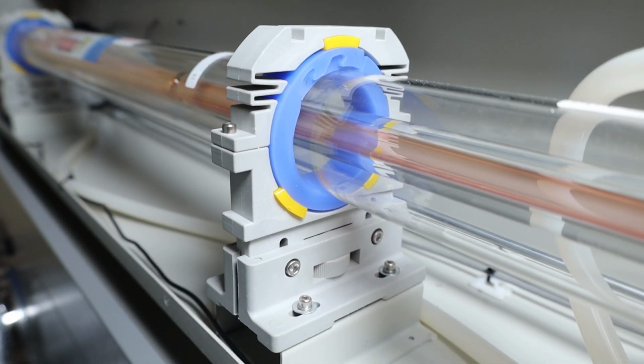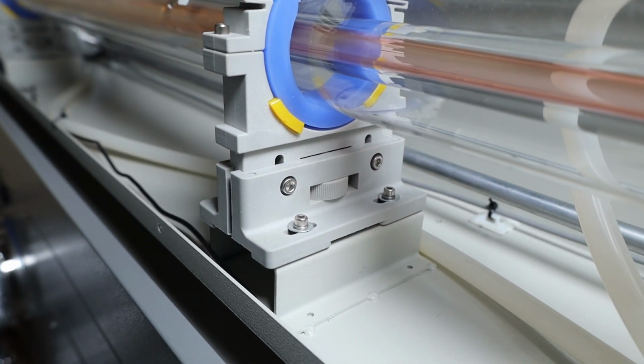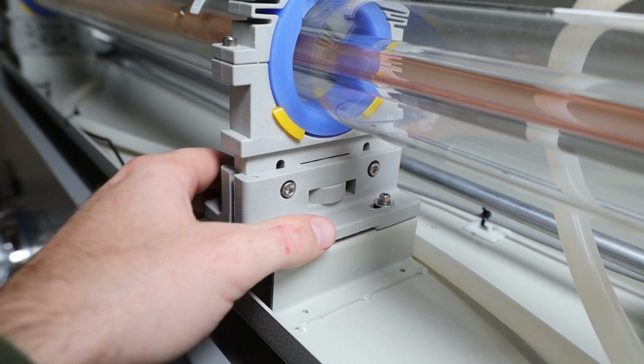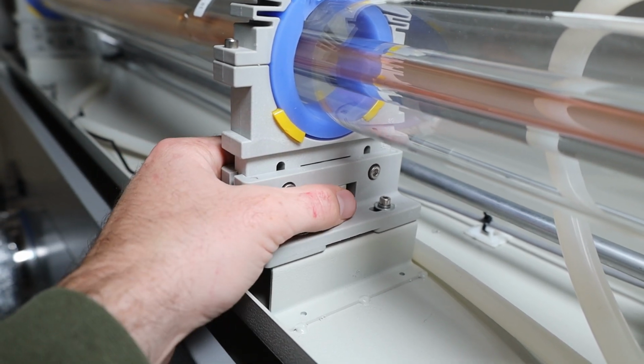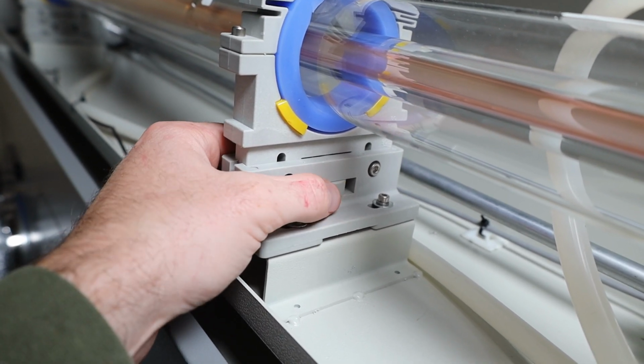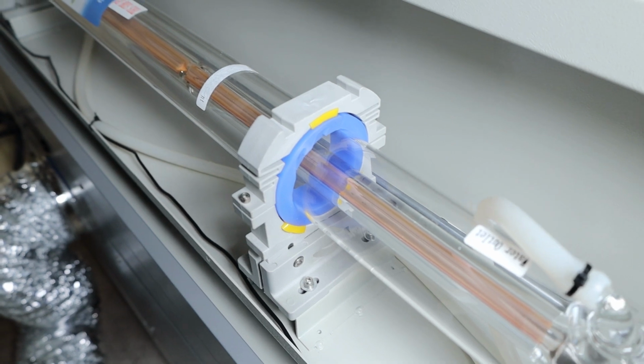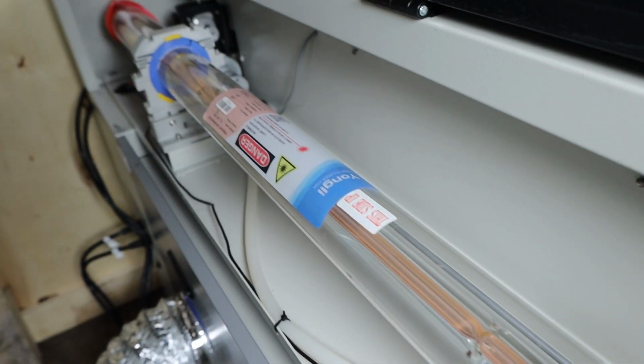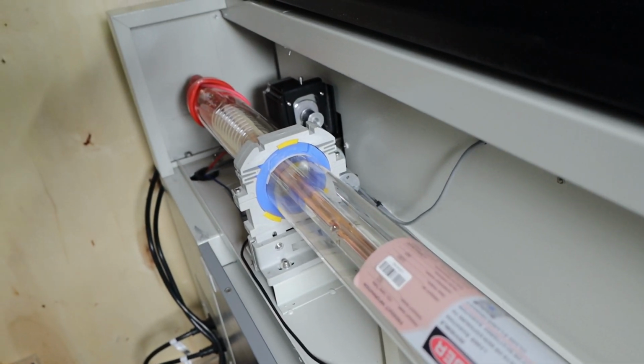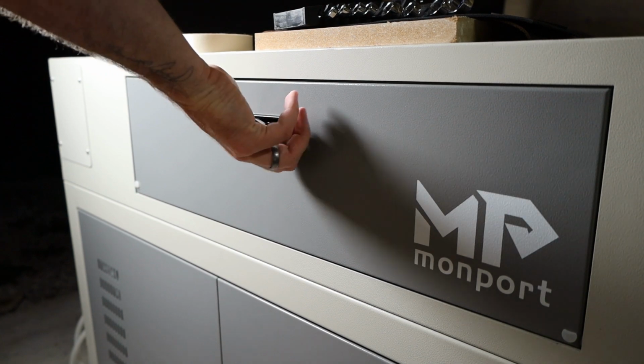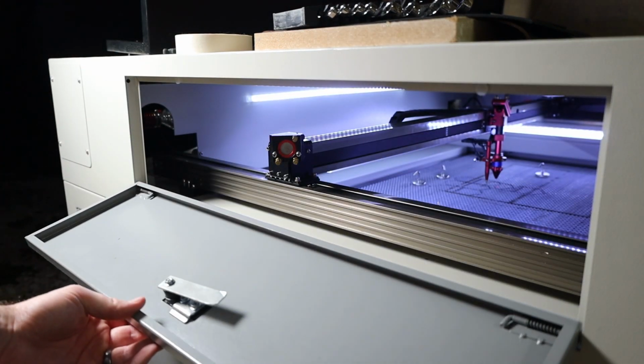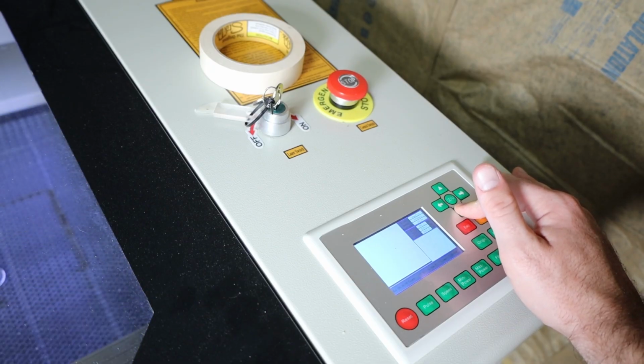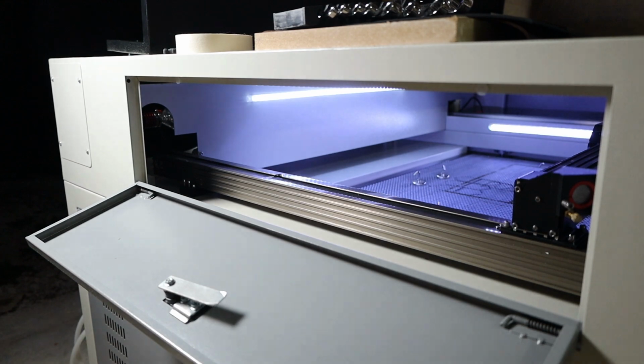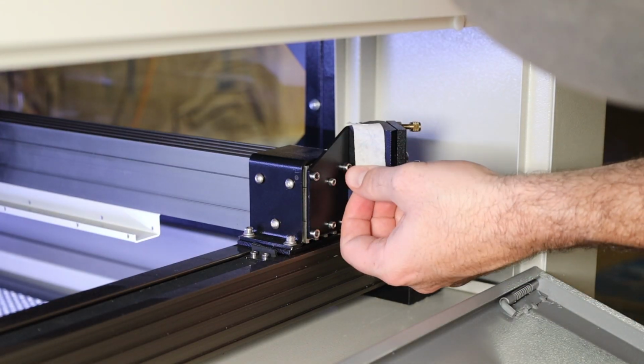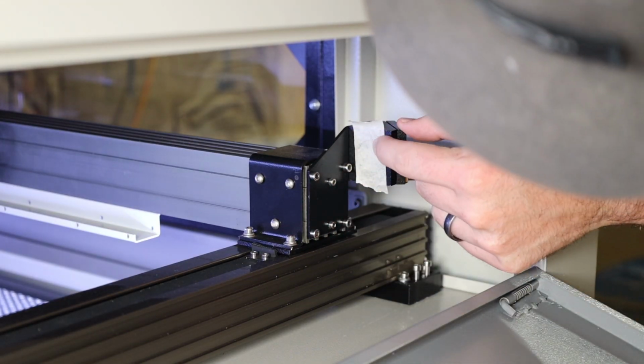If it's not centered, you can adjust the laser tube up, down, left, or right using the thumb screws under the tube until the pulse puts the hole right in the middle of the circle. Make sure to adjust both the front and back thumb screws evenly so the laser tube itself is level. Once you've centered your little dot, move the laser head all the way to the front of the work area using the arrows on the control pad and put a small piece of tape on the next mirror, which can be accessed from the side panel, and fire off another pulse.